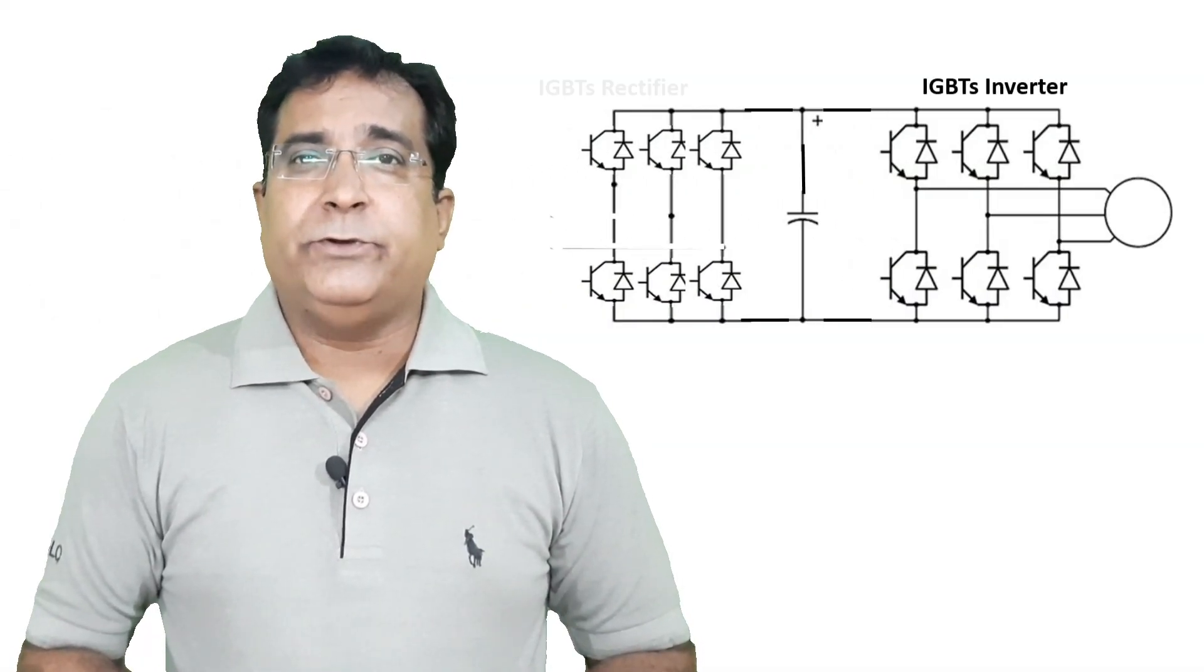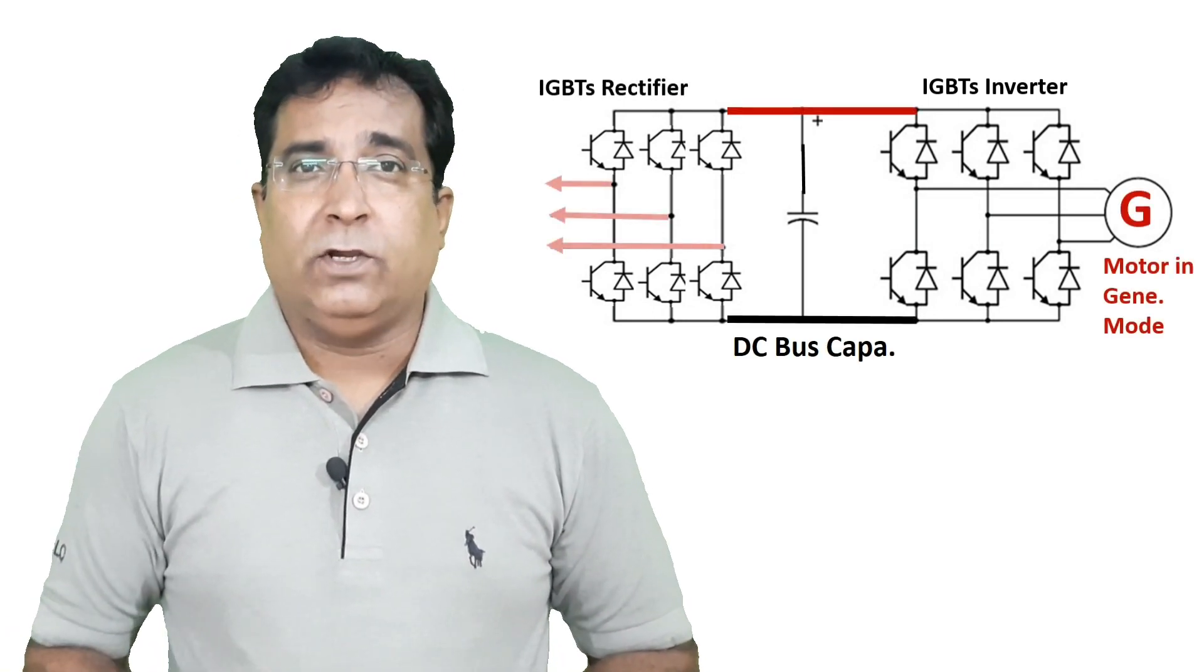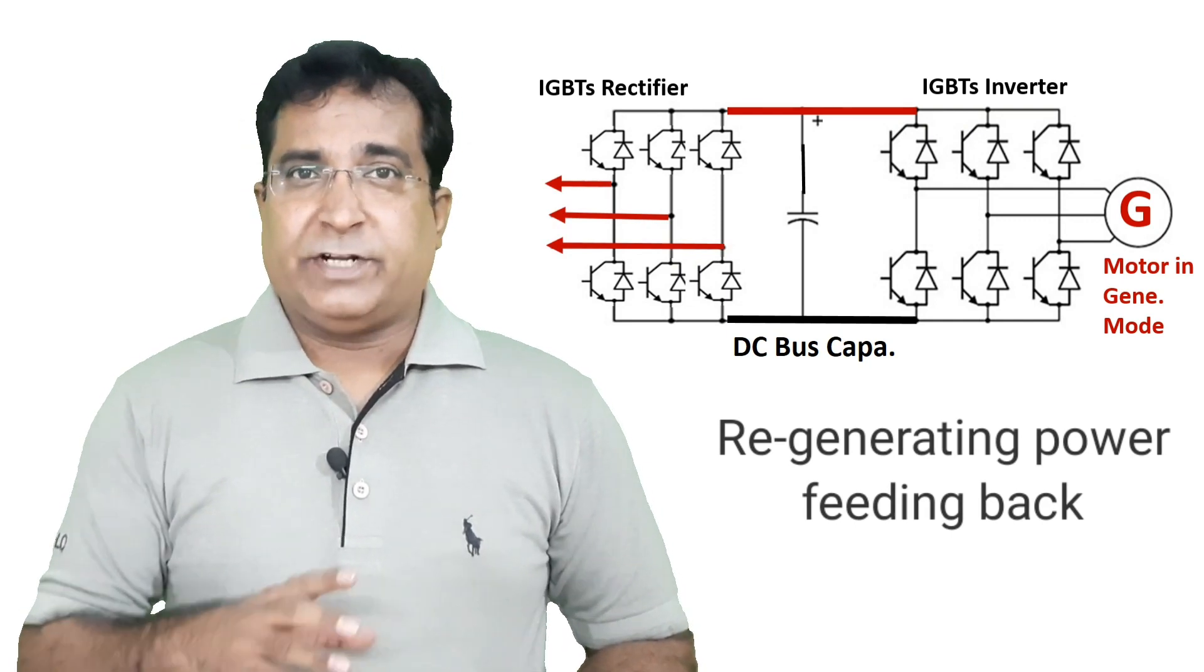Rather wasting this energy as heat it is better to feed this energy back to power system. But for this application you need a VFD that have controlled bridge rectifier built with IGBT, so that reverse power flow can take place. A VFD with diode bridge is unidirectional, you don't have choice to feed back this energy. So you are left with the option of wasting energy as heat.